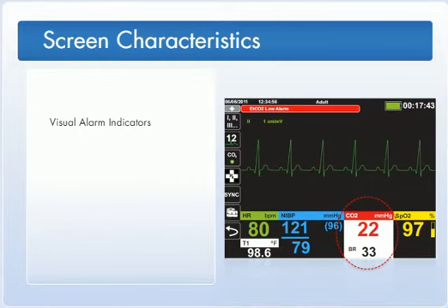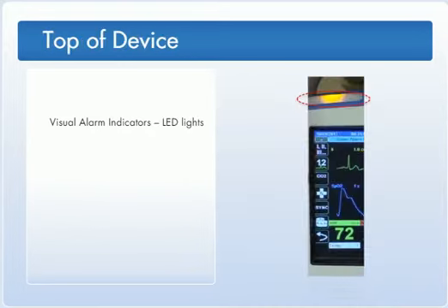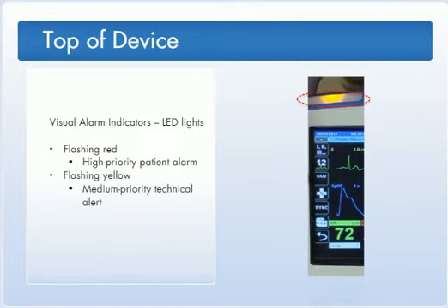The X-Series lets the user know of an alarm situation in a number of ways. The parameter window indicator shows the alarming parameter in red against a white background. There are also LED lights on the top of the device that are visible from both the front and rear. Red, yellow, and green lights located on the top of the unit flash on and off when the unit is powered up and are used to indicate a patient alert, equipment alert, and data transfer. Flashing red means a high priority patient alarm. Flashing yellow means a medium priority technical alert, and a continuous yellow, low-priority technical alert.